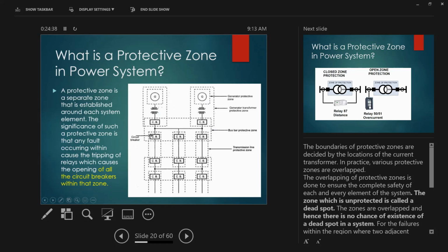This busbar protective zone doesn't care about the fault of overcurrent, doesn't care about the fault on the transformer. It is only caring about this bus. Once there is any fault in that bus, this bus protective zone will trip all 5 breakers, or doesn't matter, 20 breakers, or I think the last one that we did, I think that's the rule of thumb.